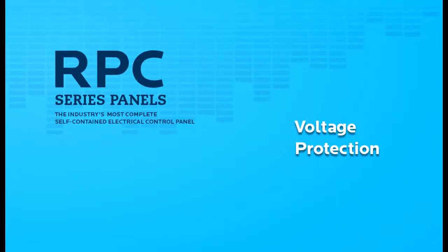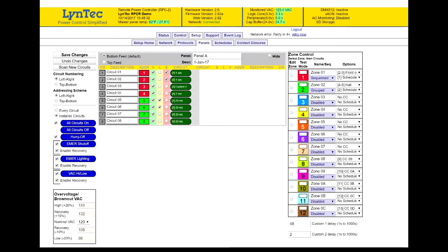Voltage protection has similar options to emergency shutoff, but is invoked not by contact closure, but instead by over or under voltage conditions or loss of power. Make voltage protection active by checking the V box. Choose the nominal voltage that is correct for your system and specify whether you want circuits to remain off or recover after loss of power.